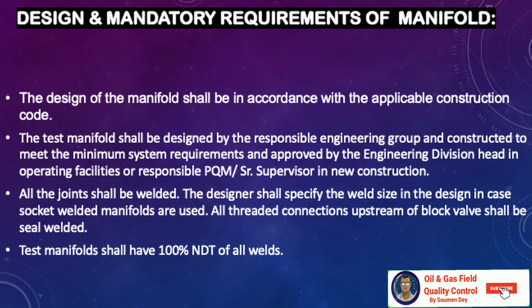The design of the manifold shall be in accordance with the applicable construction code. The test manifold shall be designed by the responsible engineering group and constructed to meet minimum system requirements, and approved by the engineering division head or responsible project quality manager. All joints shall be welded, with weld sizes specified in the design for socket weld manifolds. All threaded connections upstream of block valves shall be seal-welded. The test manifold shall have 100% NDT for all welds.